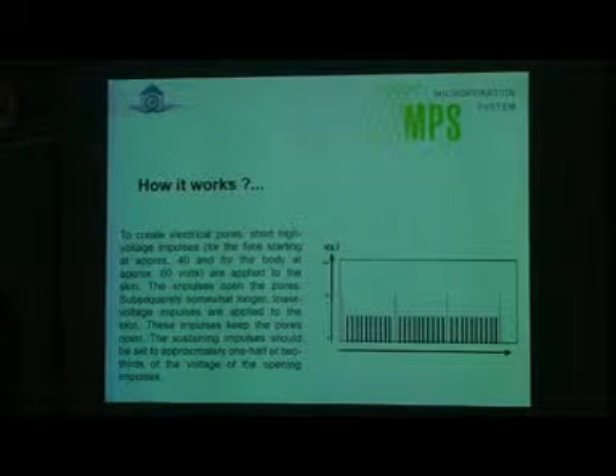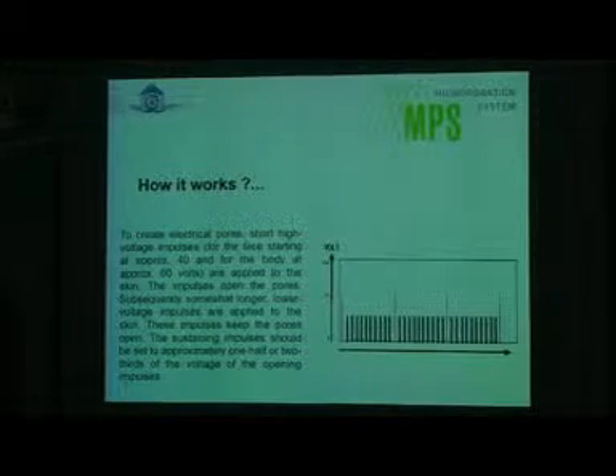So if pulses, as I have shown, of about 60 volts are applied to the stratum corneum, there's a rapid reduction in the electrical resistance of the skin, allowing more electrical power to pass through. And this causes an opening of these channels in the stratum corneum, allowing the introduction of the substances transdermally into the deep layers of the skin. So how does it work? To create these electrical pores, we have these short high voltage impulses, 40 volts for the face, 60 volts for the body, to open the pores, and then to keep the pores open over a period of time.